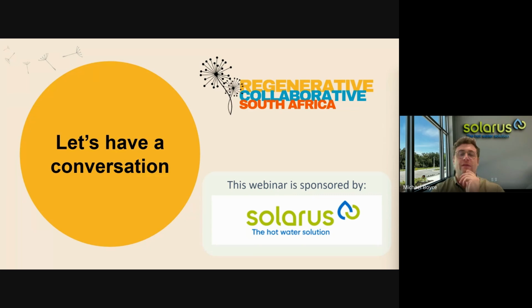Seasonal COPs: as shown in one slide, the energy balance on an annual basis deteriorates over the year. In summer months we meet 100% of demand with solar thermal. In winter months we preheat water as high as possible. Currently grid water comes in at 16 to 18 degrees Celsius. If we preheat that in winter with PVT to 30-35 degrees Celsius, getting the delta from 35 to 50 degrees requires less work from the heat pump. That's why we also increase the lifespan of the heat pump while increasing its COP at the same time. Hope that answers your question, Graham.